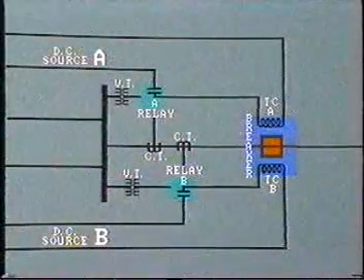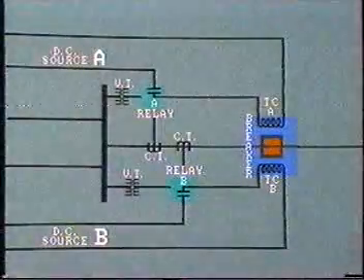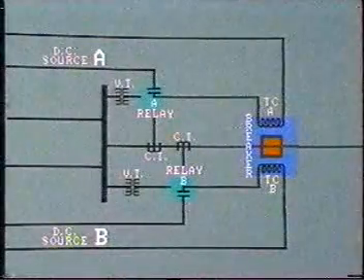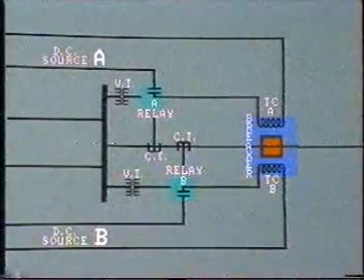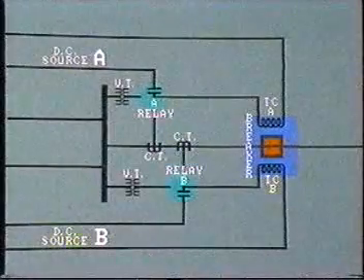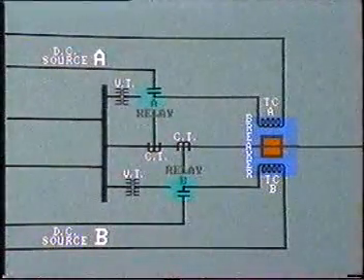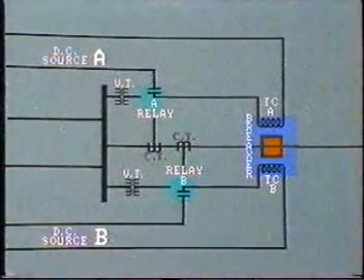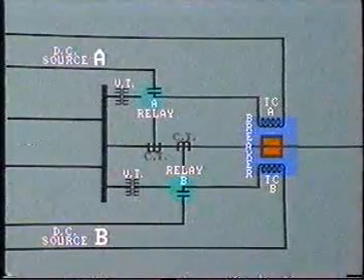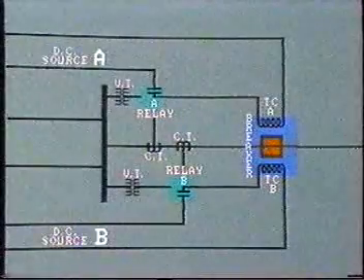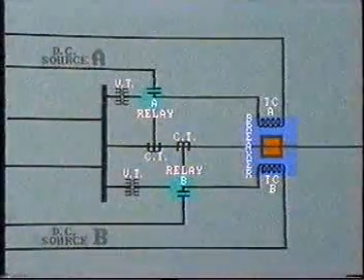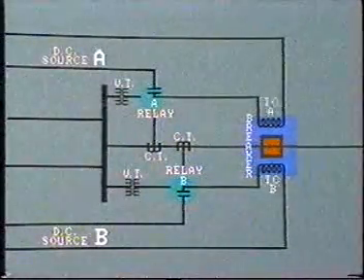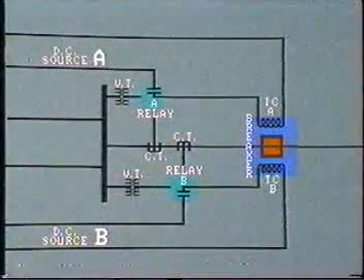Nowadays, more emphasis is being placed on local backup. Several types of protection are provided for each zone, and frequently a duplicate, so-called redundant, installation of identical relays is provided. This would be fed by separate CTs and a separate source of DC tripping current. This, in turn, will be fed to separate tripping coils within the breakers.